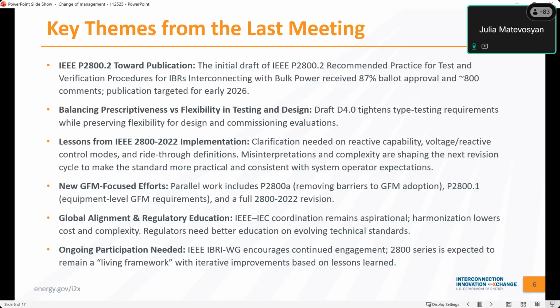With regards to lessons learned from IEEE 2800 2022 implementation, there were some identified issues where clarification is needed, specifically with regard to reactive capability, voltage reactive control modes, and ride-through definitions. And so all of these misinterpretations and complexities will be shaping the next revision of the standard. So we are basically compiling a list of issues that we will work on when revising IEEE 2800.